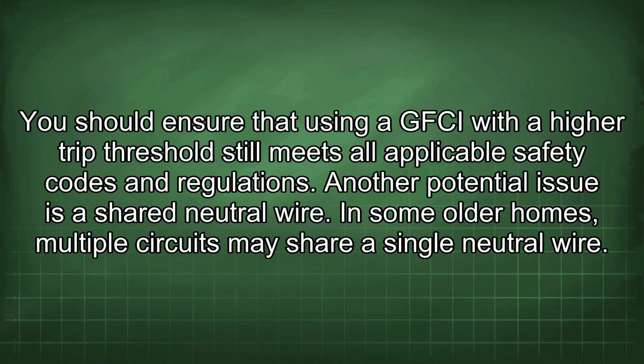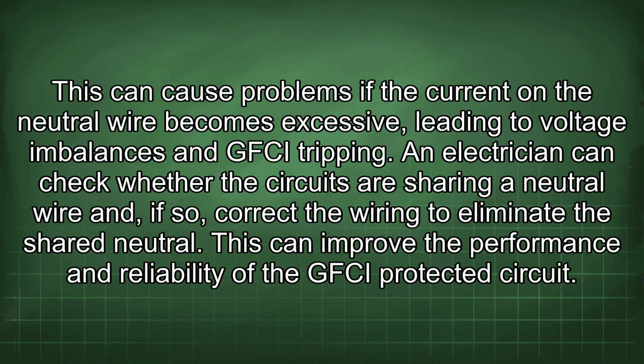Another potential issue is a shared neutral wire. In some older homes, multiple circuits may share a single neutral wire. This can cause problems if the current in the neutral wire becomes excessive, leading to voltage imbalances and GFCI tripping. An electrician can check whether the circuits are sharing a neutral wire and, if so, correct the wiring to eliminate the shared neutral. This can improve the performance and reliability of the GFCI protected circuit.